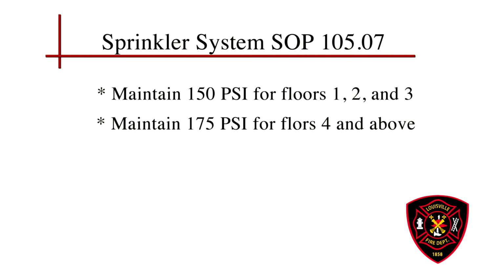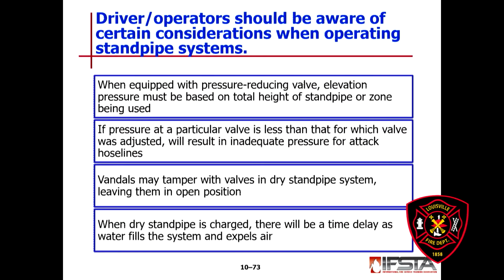Some things you need to take into account when equipped with a pressure reducing valve: the elevation pressure must be based on the total height of the standpipe or the zone being used. If the pressure at a particular valve is less than that for which the valve is adjusted, it will result in inadequate pressure for an attack. So we may have to adjust that, and we have the capability to adjust a PRV with that tool in our high-rise kits.